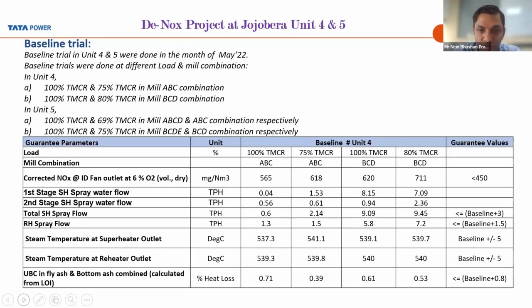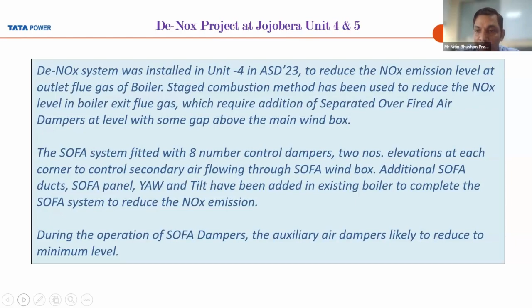This is our system. This is basically the stage combustion method that has been used to reduce the NOx level in the boiler exit flue gas, which requires the addition of the sofa dampers at a level some gap above the wind box. The sofa system is fitted with 8 control dampers, 2 elevations at each corner, to control the secondary airflow through the sofa wind box. Additional sofa ducts and sofa panel are the extra equipment that have been installed in the sofa system. Then the yaw mechanism and tilt have been added in the existing boiler to complete the sofa system to reduce the NOx. During the operation of sofa dampers, the auxiliary air dampers are likely to reduce to the minimum level. Kindly move forward.